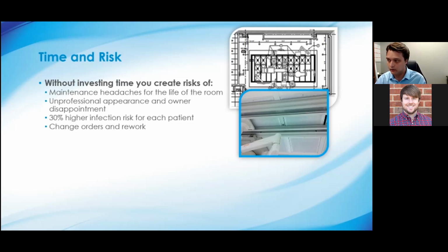The problem here is twofold. First, this equipment disrupts the laminar flow air out of the diffuser, negating any protection it was meant to provide the patient. Second, it's a maintenance headache for the life of the room, because the faceplates are no longer accessible to clean off splatter, and if there's a filter inside, it can't be changed without taking down all the imaging equipment. It's a huge headache that sticks around until another renovation project fixes it.